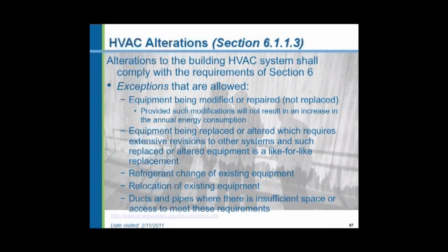You're not required to comply with the new energy code if you're simply replacing refrigerant. Or you're relocating a furnace. Maybe you're moving something out of the way to provide a better access. Existing equipment simply moved a little bit, you don't have to worry about it. And ductwork and piping where there's not sufficient space or access to meet the new code. You simply cannot get the required level of insulation around the pipe because there's no space in the chase. You don't have to comply.